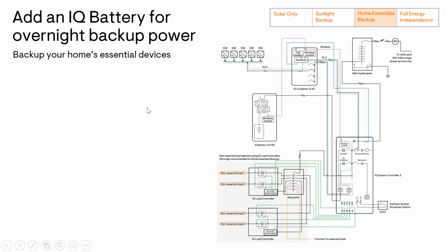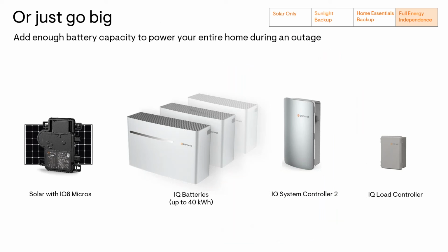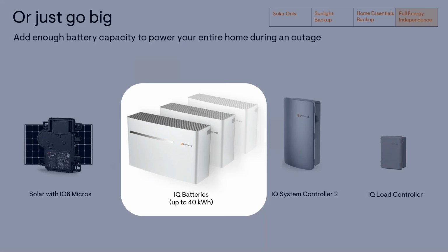And a simple single line here of the Home Essentials backup. So all the components that we had with a sunlight backup system, but now we've added an IQ battery right here. And our last configuration we call the full energy independence configuration. This is very similar to the Home Essentials backup. The only real difference is the size of the battery connected to the system. Obviously, by the name, the system is designed for whole home backup. And up to 4 IQ battery 10s can be installed with each System Controller 2, so that would be up to 40 kilowatt hours of capacity.